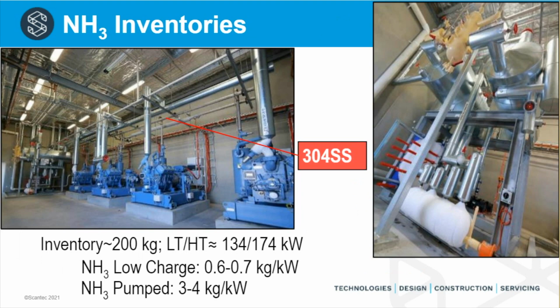This is an image from a plant in South Australia that was installed about 5 years ago. You can read the data there yourself. This plant has an inventory that's approximately 4 or 5 times lower than the equivalent liquid overfeed system. It uses reciprocating compressors, and it uses glycol, reticulated glycol, for the medium temperature service. This is one of the reasons that the inventory in this plant is relatively low at 200 kilos.